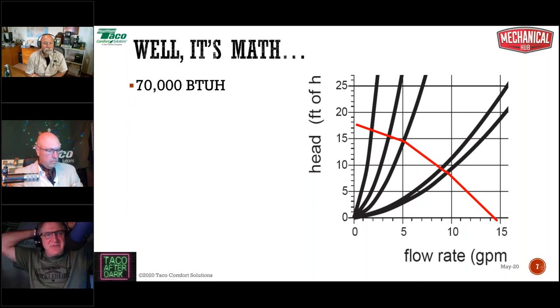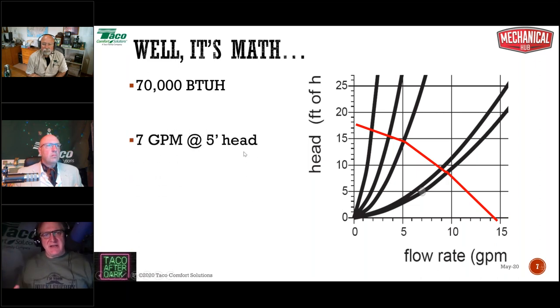So let's say I've got a 70,000 BTU zone valve job, 70,000 BTU house. If we apply the universal hydronics formula, which states that GPM equals BTUH divided by delta T times 500, and we're designing a typical North American system to a 20 degree delta T, 70,000 divided by 20 times 500. If we presume 100% water, 20 times 500 is 10,000, and 70,000 divided by 10,000 gives a required flow rate under design conditions, coldest day of the year for this job, of 7 gallons per minute.